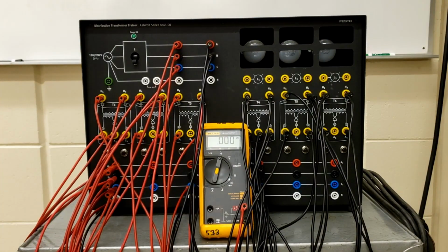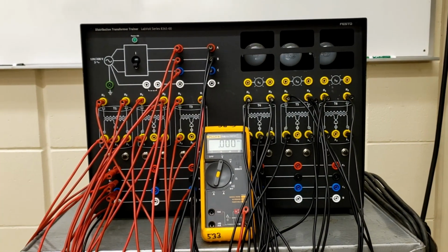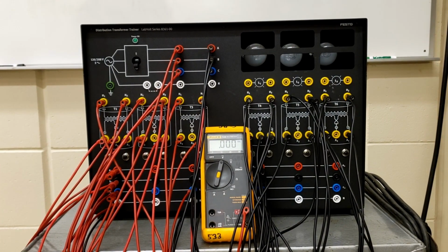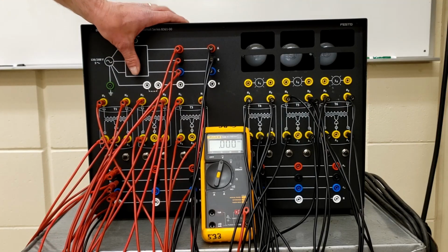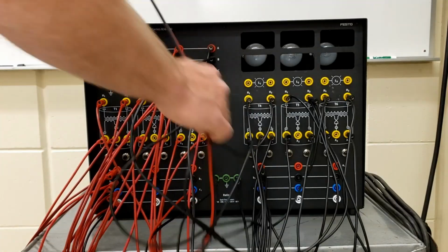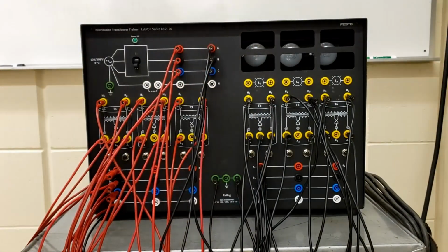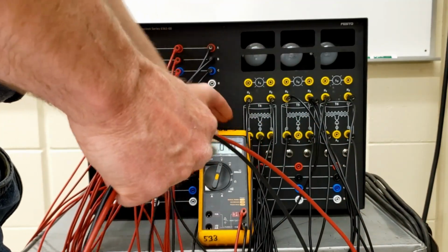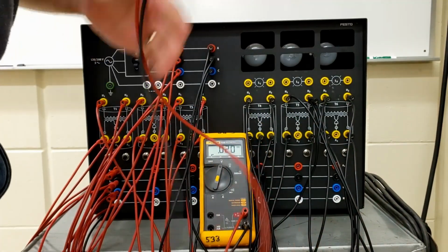Okay, so on the bottom of that page it says turn on the distribution transformer and read the voltage between A2 and B2, B2 and C2, C2 and A2, and then A2 and neutral, B2 and neutral, C2 and neutral. So let's do that, let's get this guy up and running. This is connected up to my previous transformer, so let's take a look between the two output phases of this second transformer here.